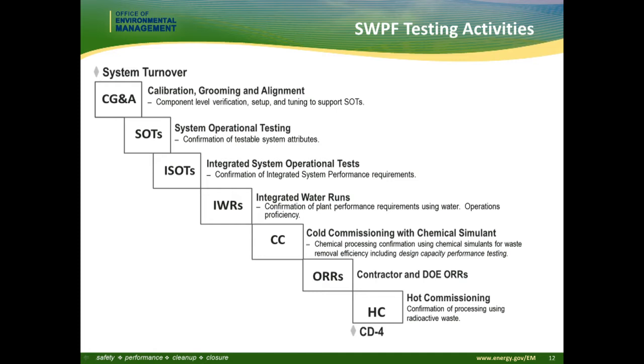We have 60 system operational tests - we've broken down our entire system into 60 individual tests. Then we move into integrated system testing, which has 5 of those. So I use the analogy: I have 60 bubbles, and I have to put those 60 bubbles into 5 bubbles. A basic thought, but obviously some of those things transcend - a lot of our plant systems are going to be used and tested in all of our ISOTs.